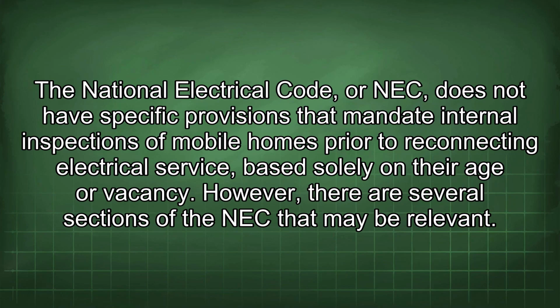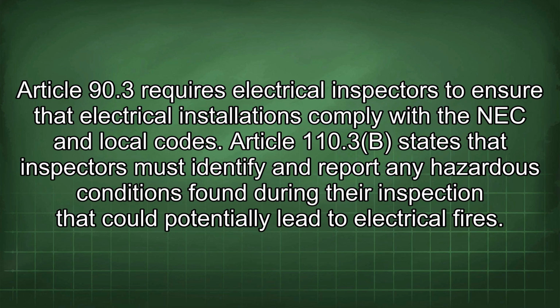The National Electrical Code, or NEC, does not have specific provisions that mandate internal inspections of mobile homes prior to reconnecting electrical service based solely on their age or vacancy. However, there are several sections of the NEC that may be relevant. Article 90.3 requires electrical inspectors to ensure that electrical installations comply with the NEC and local codes. Article 110.3b states that inspectors must identify and report any hazardous conditions found during their inspection that could potentially lead to electrical fires.